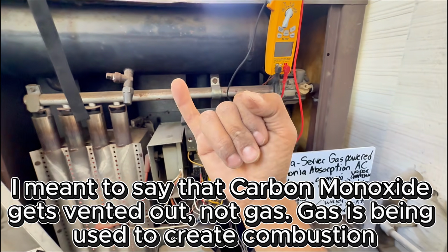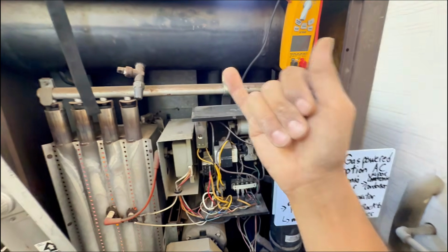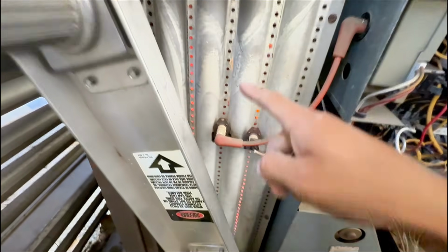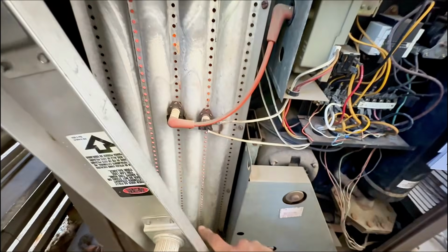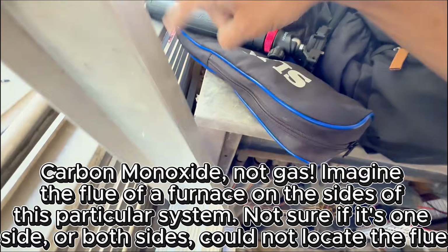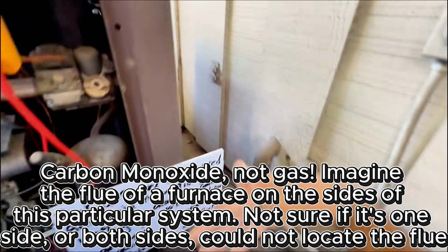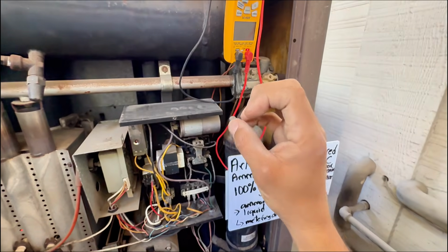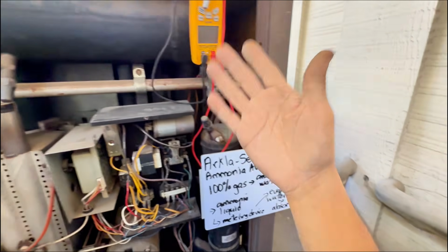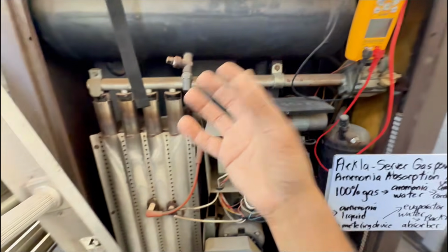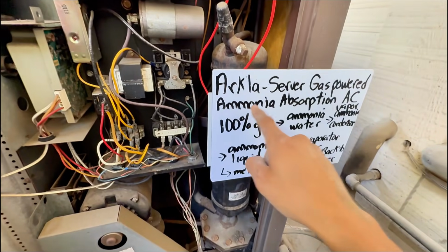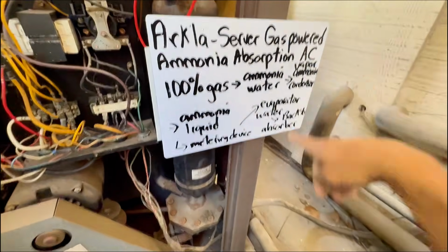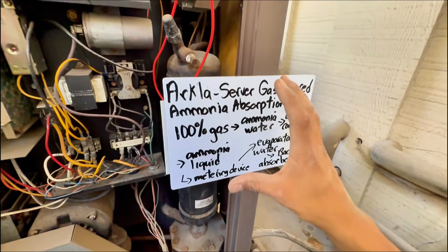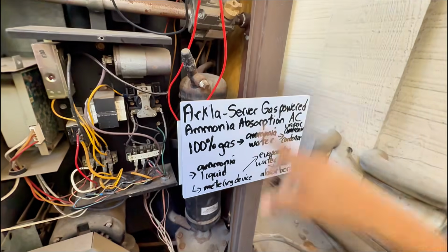So it's not natural-gas friendly. You just have gas coming in. It does its combustion, as you can see. Look at all the burners. Look at all the flames, right? You see all that right there. You got your gas valve, 24 volts, and then the gas is seeping out through the sides, right here, and it's just coming out. So you can say that it's a 0% furnace, right? 100% of the gas gets vented out, but they're using the flames, that heat, to manipulate the ammonia. So you have this thing called an absorber, and inside that absorber, you had ammonia and water kind of just sitting together.